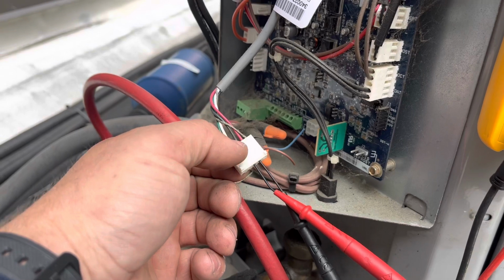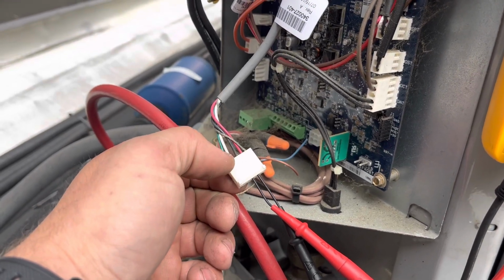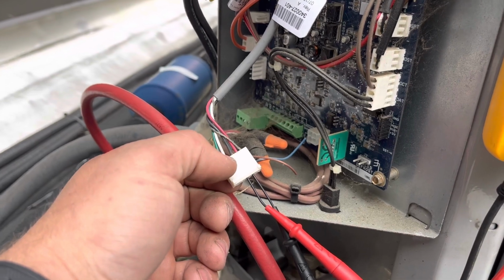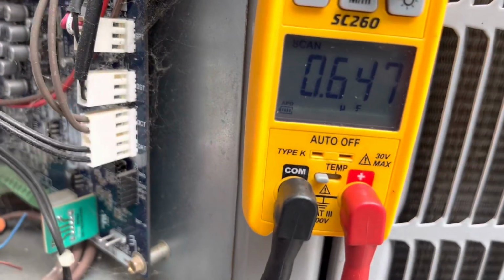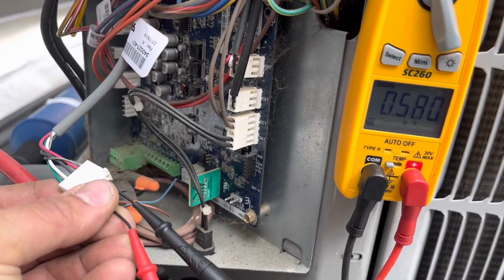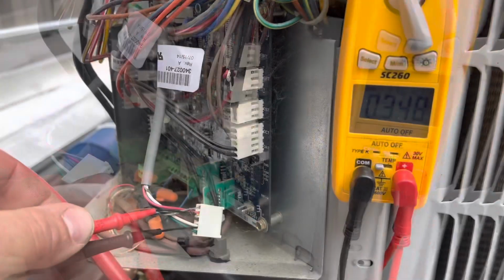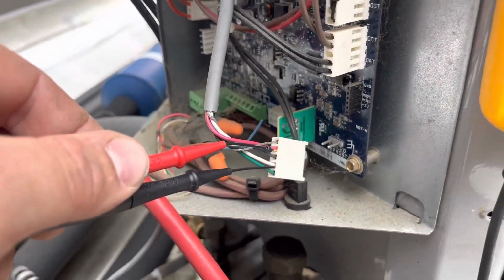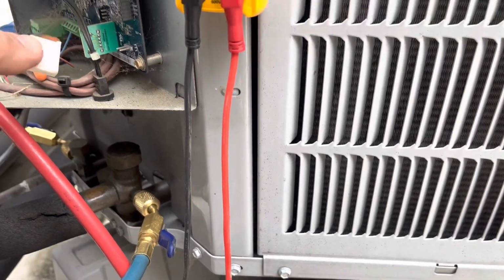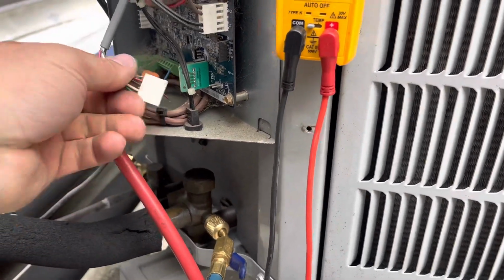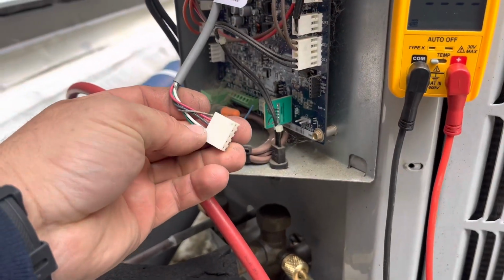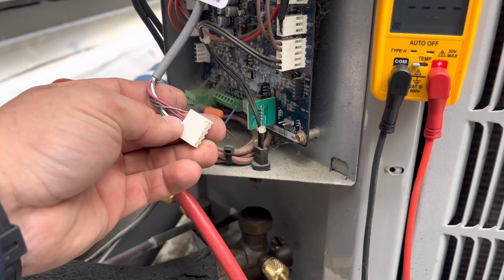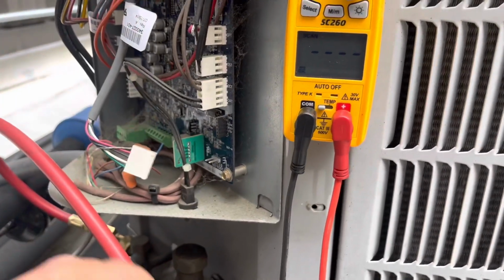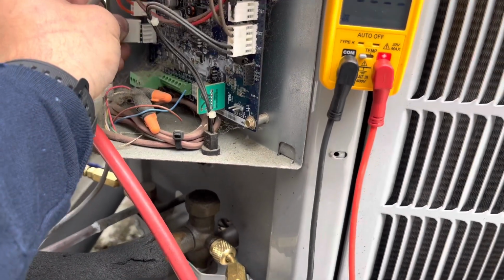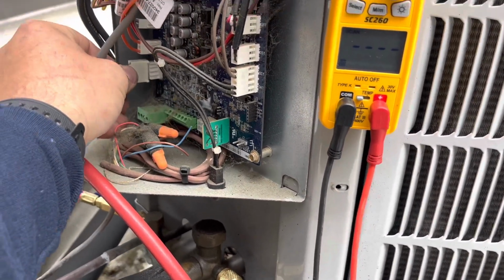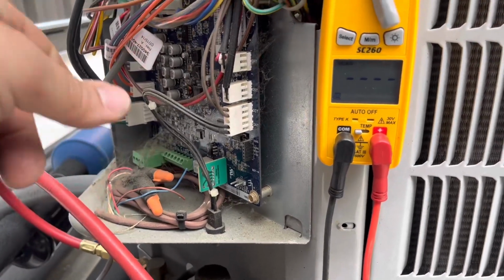Turn this off. All right, so I'm gonna do black to red, red to white, and black to white. So right now I have red to black, white to black, and I'll do white to red. White to red. So after looking this system up in the Carrier app, I'm supposed to have 0.203 across each white to red, white to black, and black to red. And I'm all over the place. In the diagnostic, it said it could be my compressor and my inverter board.